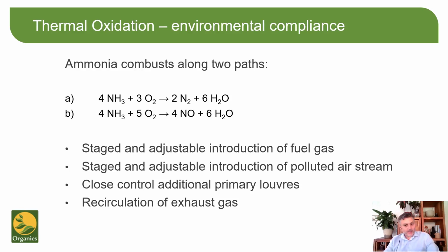We have found that by straying by as little as 40 degrees centigrade from the ideal combustion temperature, we can lead to high levels of NOx in our exhaust stream. And finally, we have the capability to recirculate some of the exhaust gas back into the base of the thermal destructor. This allows the exhaust gas to be used to keep the temperature within acceptable limits, but without introducing the additional oxygen that atmospheric air would introduce. Using the exhaust gas as cooling gas reduces the amount of additional oxygen available, and so reduces the possibility of NOx forming, whether that be high temperature NOx or ammonia-related NOx.